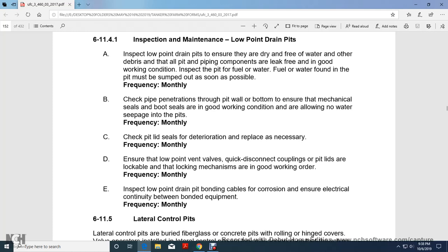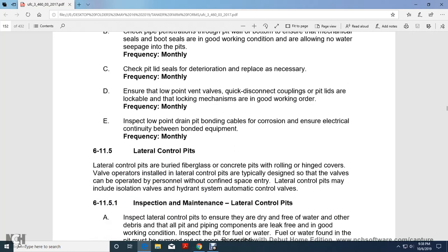Check the pit lids for deterioration and replace as necessary, monthly. Ensure the low point vent valves, quick disconnect couplings, and pit lids are lockable and locking mechanisms are in good working order, monthly. Inspect low point drain pit bonding cables for corrosion. Ensure electrical continuity between the grounded equipment, monthly.